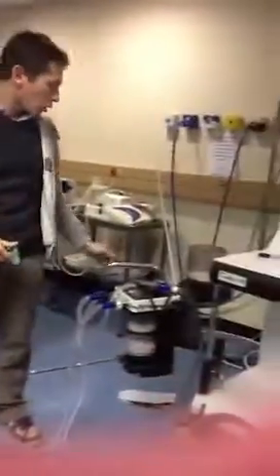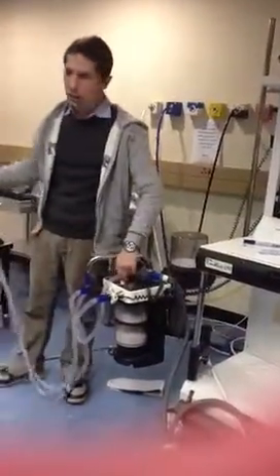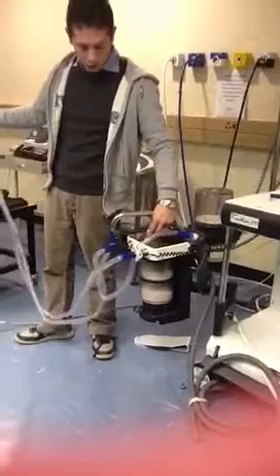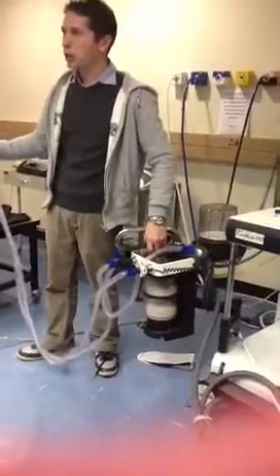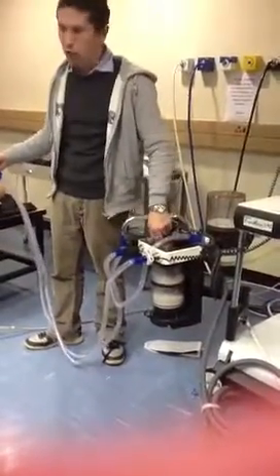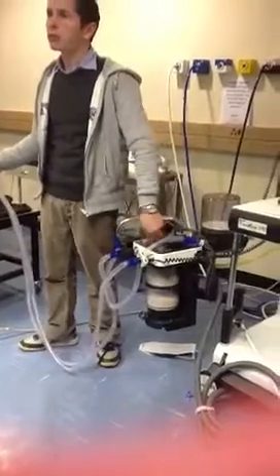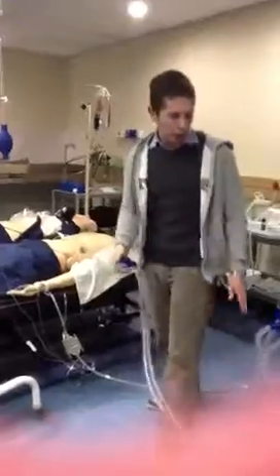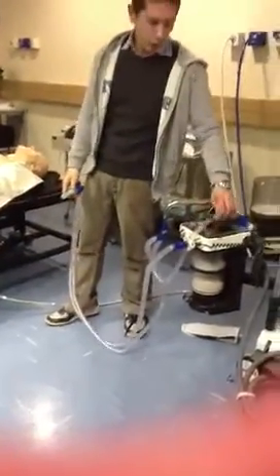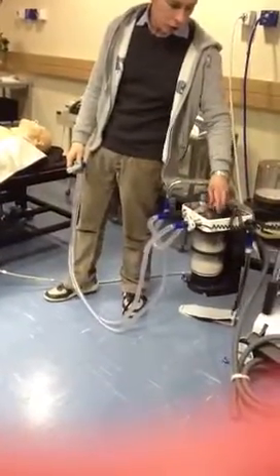Right. These machines are still old. The oxygen sensor is a bit away from the patient. Okay, it still measures it on the inspiratory limb, so it's not that bad. But modern ventilators, you see, they measure it right at the patient end, not closer to the machine.